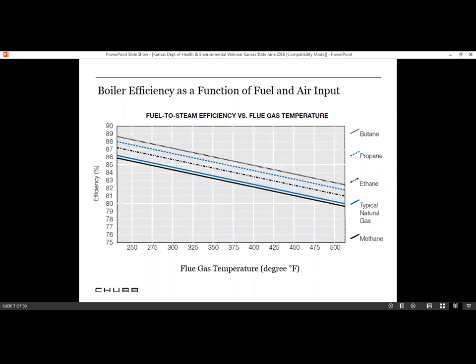If you look at this graph, you'll see the boiler efficiency as a function of fuel and air input. What I want to get across on this is, let's use natural gas as a fuel. If you look at 85% efficiency, your exhaust stack temperature should be around 270 degrees. As your exhaust flue gas temperature goes up, your efficiency goes down.